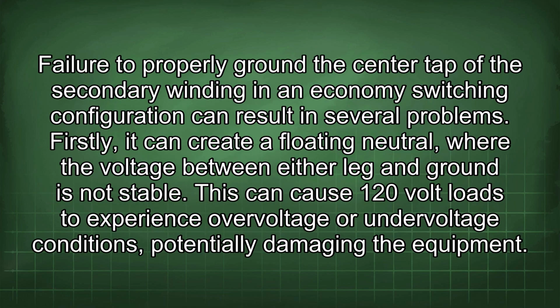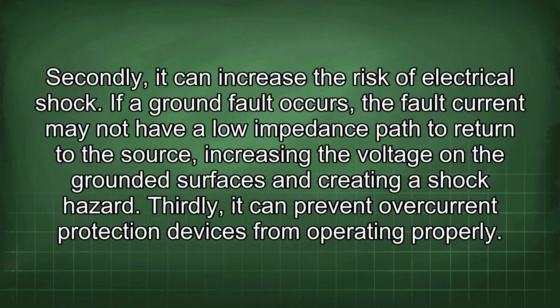Failure to properly ground the center tap of the secondary winding in an economy switching configuration can result in several problems. Firstly, it can create a floating neutral, where the voltage between either leg and ground is not stable. This can cause 120 volt loads to experience overvoltage or undervoltage conditions, potentially damaging the equipment. Secondly, it can increase the risk of electrical shock.